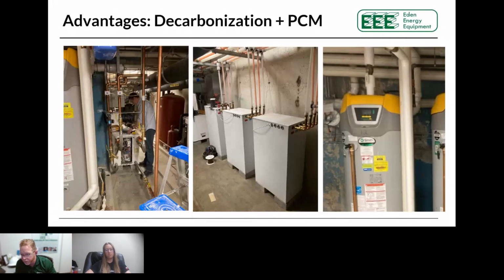We could skip the phase change step entirely, you could have the geo unit pre-charging the gas. What I'd suggest is they're using the geo unit to take advantage of off-peak rates, because we can charge these phase change batteries. The design is such that when you store the BTUs, they stay there. It's not like a water-based system because it's using sensible and latent energy. That's a really nice advantage for us.